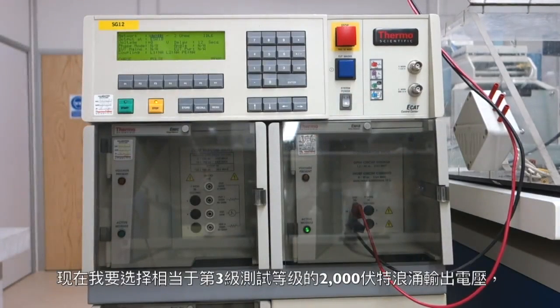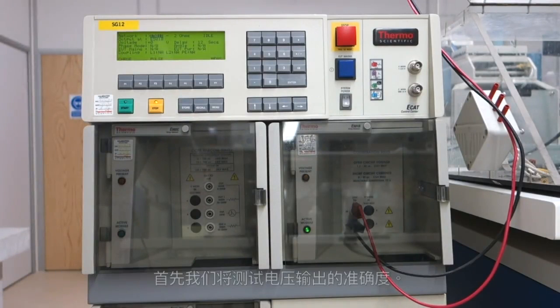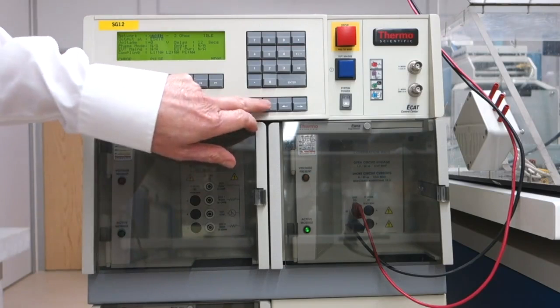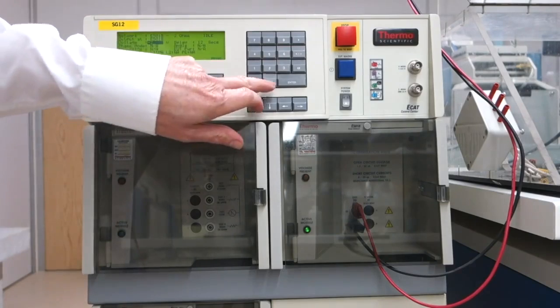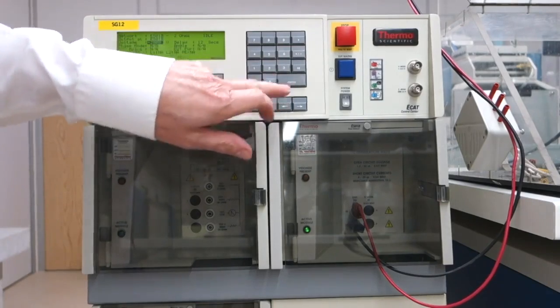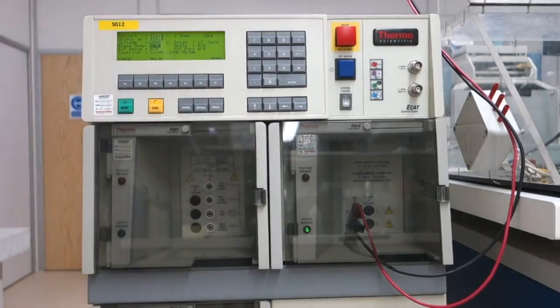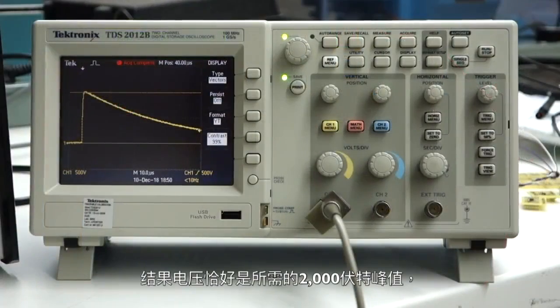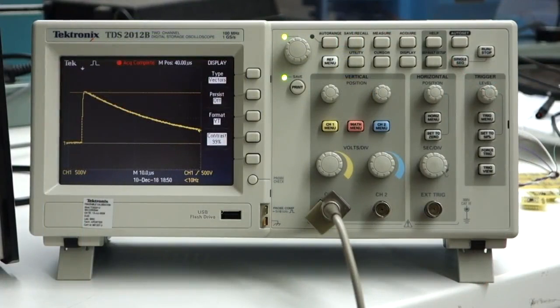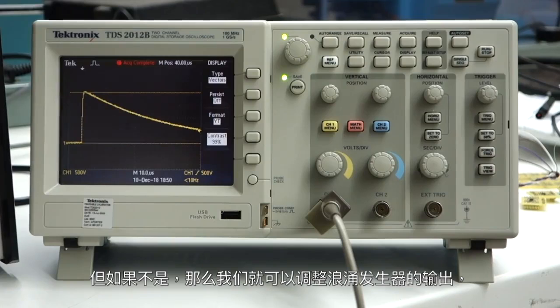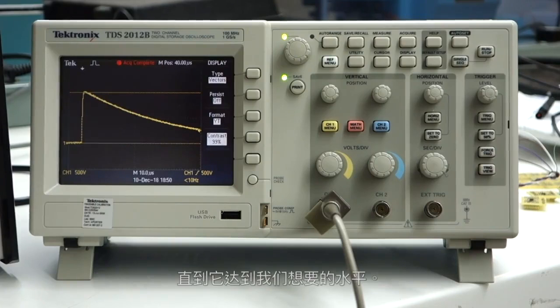I'm going to select a 2 kilovolt surge output voltage equivalent to a class 3 test, and first we'll test the accuracy of the voltage output. It happens that the voltage is spot on what is required, 2000 volts peak, but if it wasn't, then we could trim the surge generator output until it was where we wanted it to be.